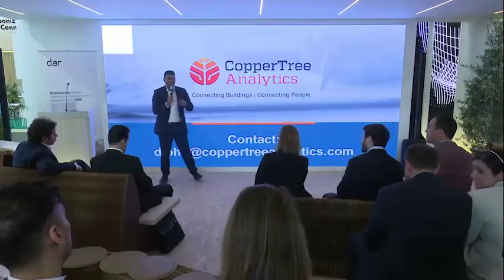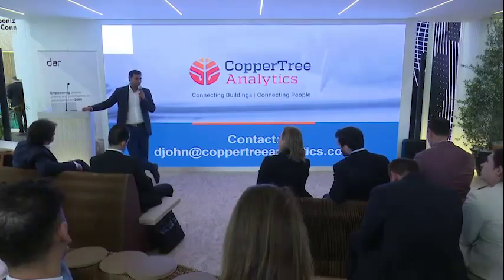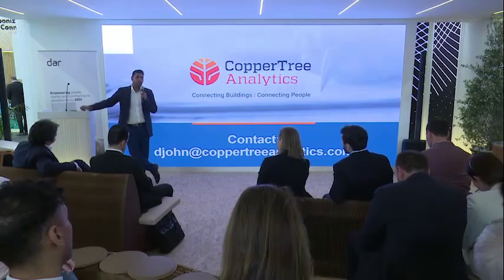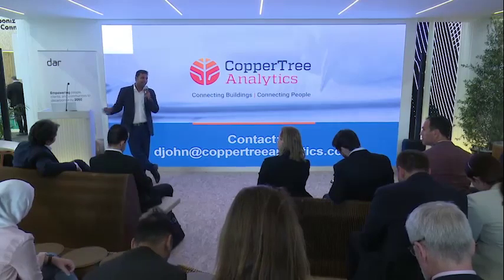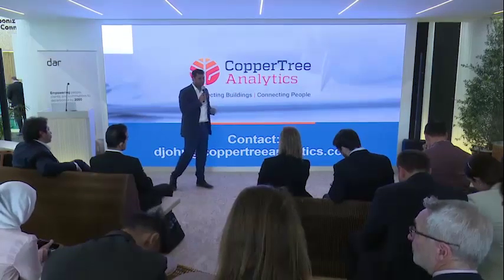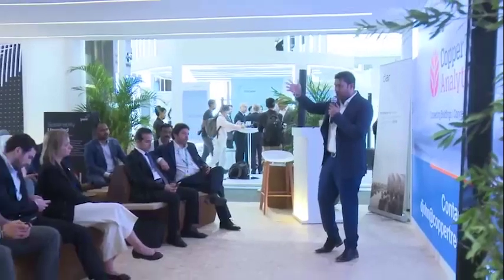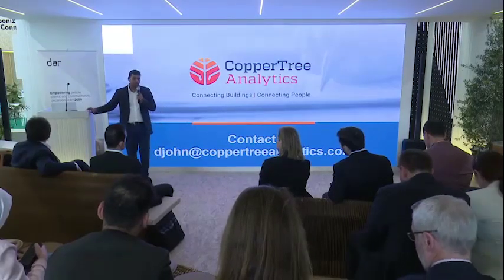Remind me if I lost a question in the mix. But I'll tackle one of the questions first, which is how you would get to savings quicker and get the payback number lower. It really is based on how many of the changes recommended by the platform are actioned. And this is where ASO becomes very important, because with automated system optimization, you can automatically write back. If there are sequence changes needed, or a pump was put in manual by an operator who forgot about it and the pump is running at a high speed all throughout, with ASO, without any human being involved, you can rewrite it. And so you can get to savings quicker. Otherwise, you are sending a work order to someone to go to the site and change it. That takes longer, and if they have other priorities, they may not get to it. So ASO, I think, is key in terms of getting to savings quicker.